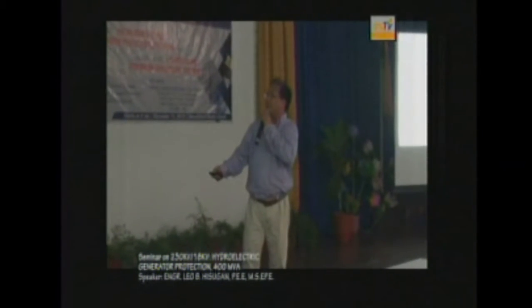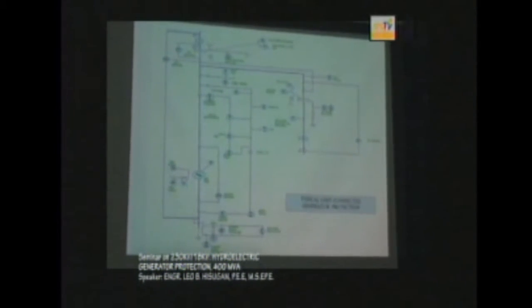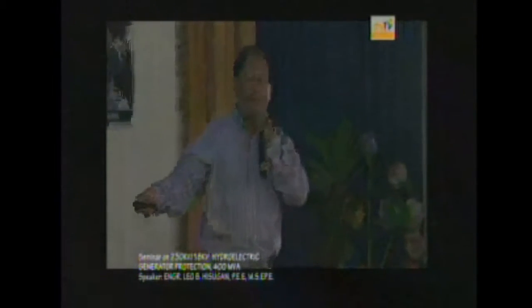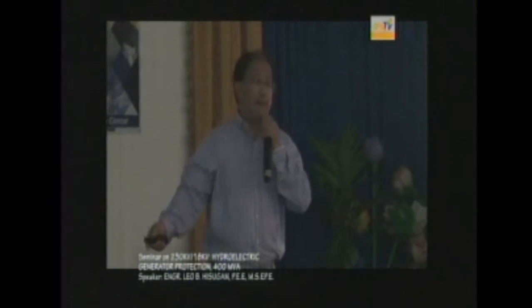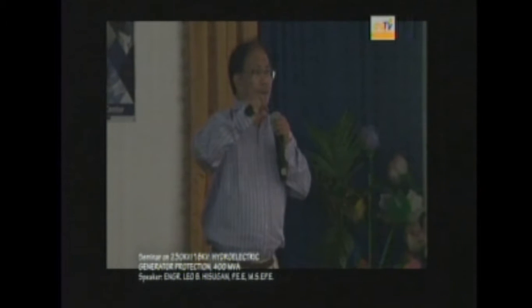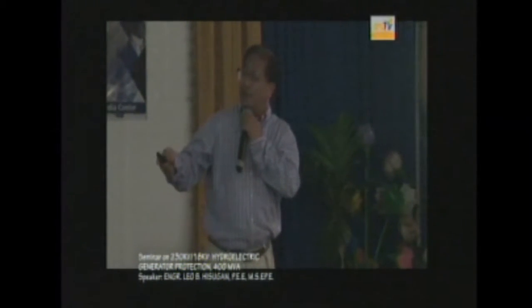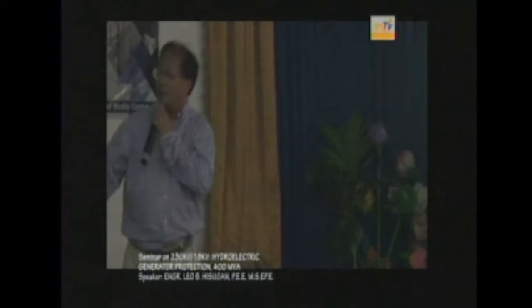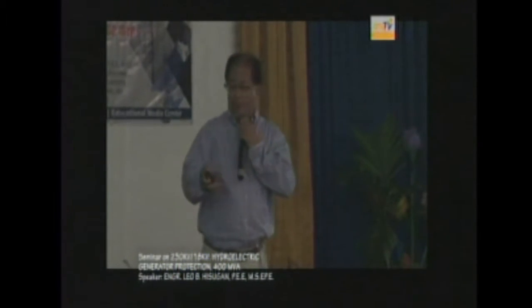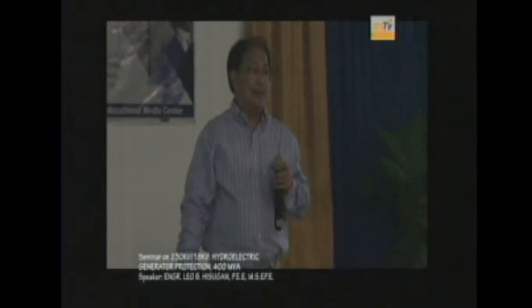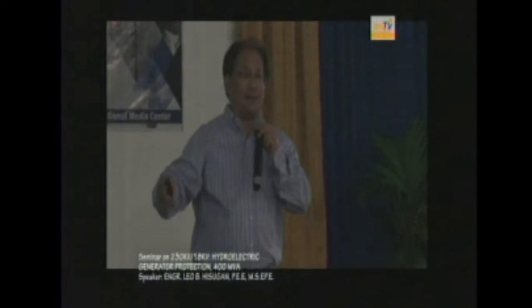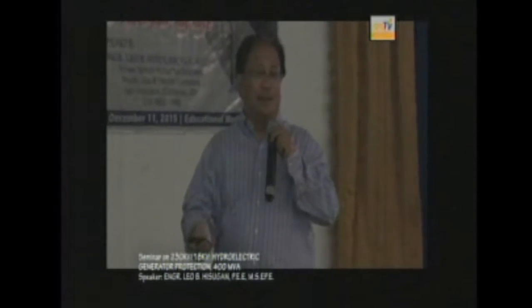So here we have this 59N device, and this is the resistor here. The 59N device is your ground over voltage relay, and this ground over voltage relay is looking at your zero sequence voltage across this distribution transformer here. And this zero sequence voltage, if you're using a three-phase system, is the summation of the phase voltages. And if you're using a single phase one here, it's the elevated zero sequence voltage of the neutral of your transformer here. Okay, normally set like 5 volts or 6 volts or 9 volts, depending on the design of your system.